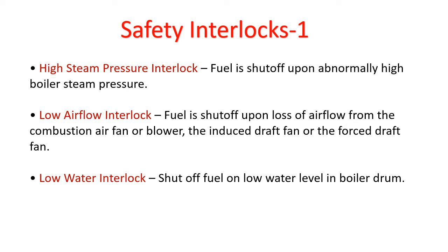Now, we are going to discuss the different interlocks. The most common interlocks are the high steam pressure interlock, where the fuel is shut off upon abnormally high boiler steam pressure. Another one is the low airflow interlock.